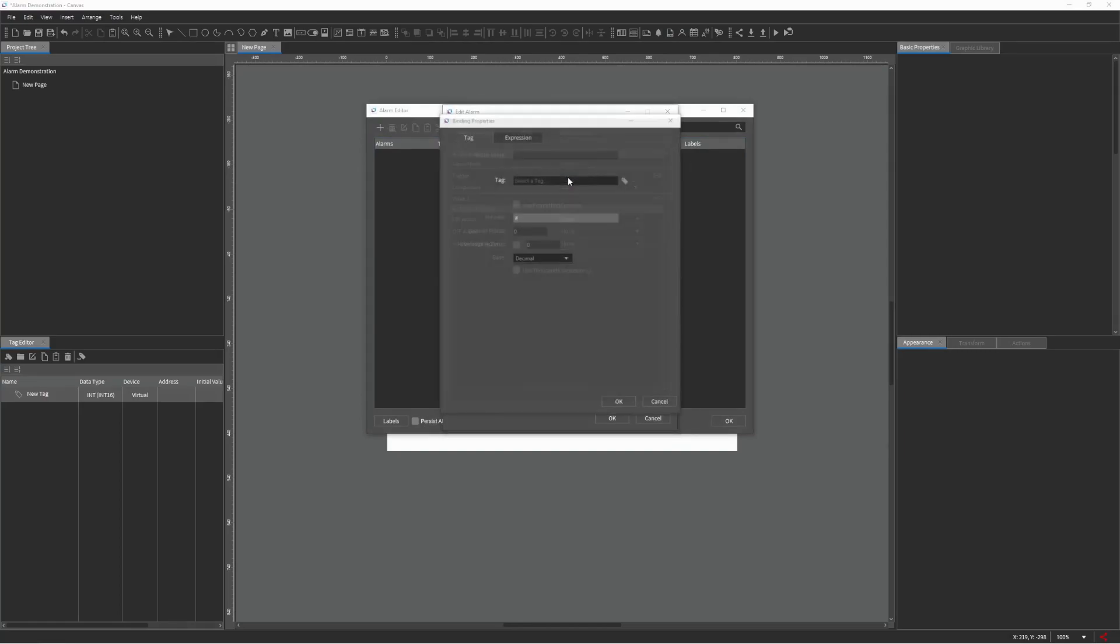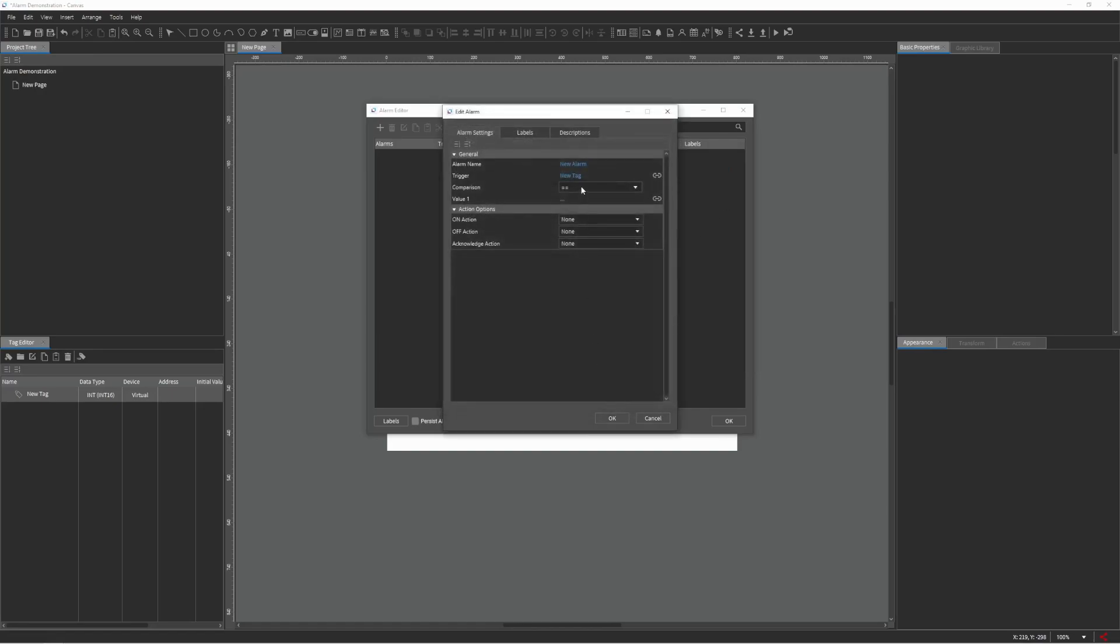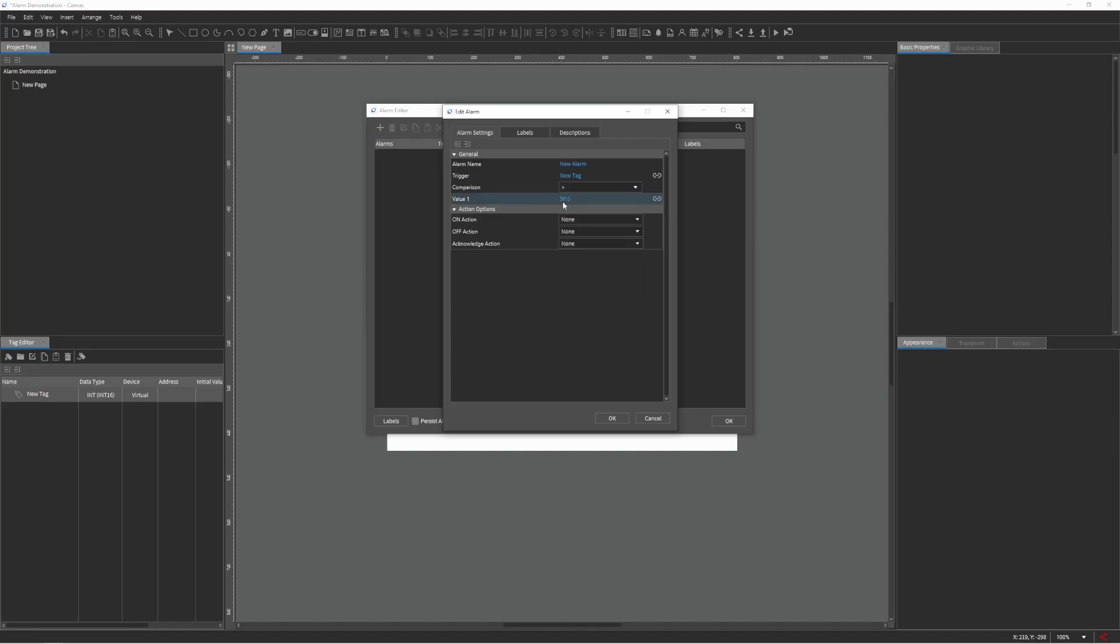We'll create an alarm by pressing the plus sign at the top left of the Alarm Editor window. Next, we will assign a tag to the trigger field by double-clicking. The comparison field will be changed to greater than, and the value 50 will be assigned to the value 1 field. Then we will press OK to confirm our settings.